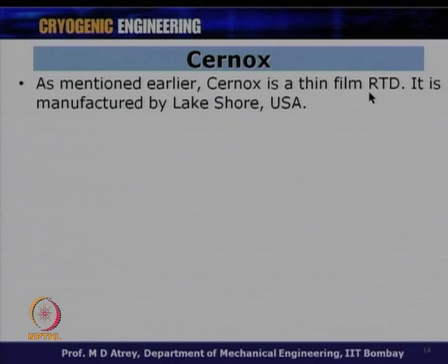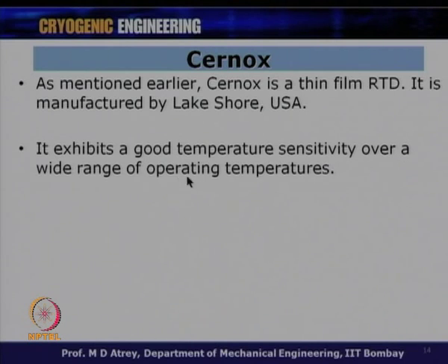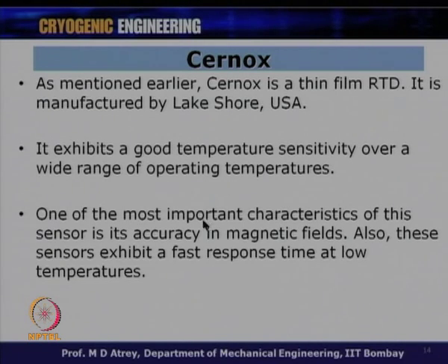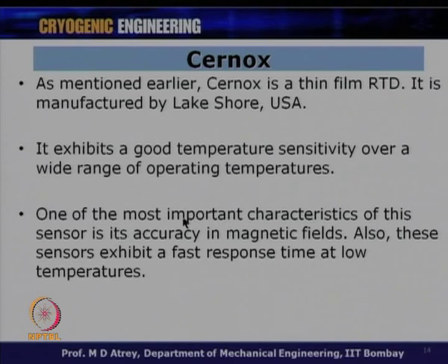The next sensor is Cernox — a thin film RTD manufactured by Lakeshore, USA. It is also a very commonly used sensor for helium temperature levels. It exhibits good temperature sensitivity over a wide operating range. One of its most important characteristics is accuracy in magnetic fields — very important since most cryogenic measurements are done in magnetic field environments such as MRI, NMR, and superconducting magnet setups. Cernox also exhibits fast response time at low temperatures.